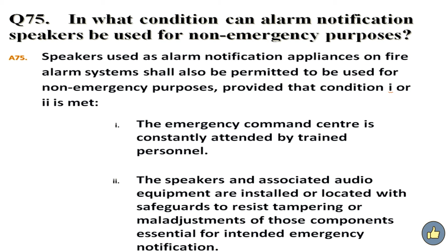In what condition can alarm notification speakers be used for non-emergency purposes? Answer. Speakers used as alarm notification appliances on a fire alarm system shall also be permitted to be used for non-emergency purposes provided that condition 1 or 2 is met. Number 1. The emergency command center is constantly attended by trained personnel. Number 2. The speakers and associated audio equipment are installed or located with safeguards to resist tampering or maladjustments of those components essential for intended emergency notification.